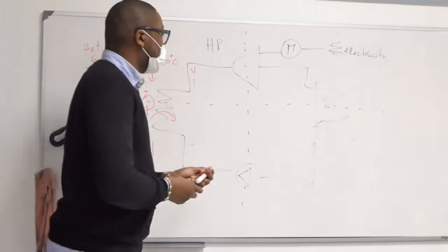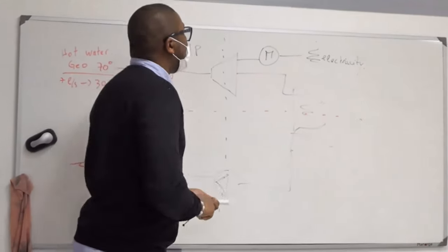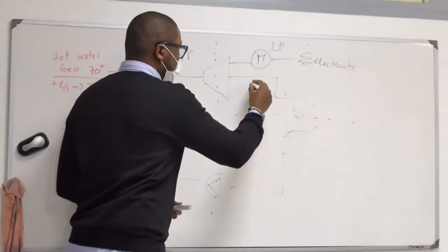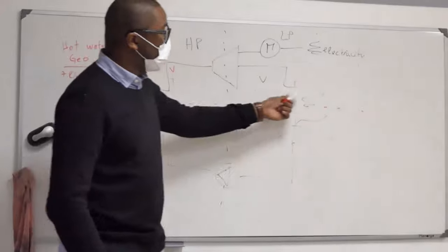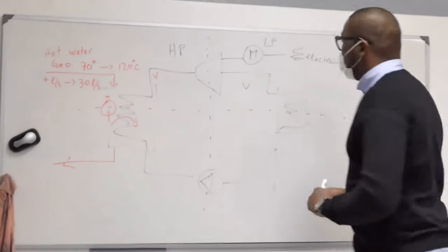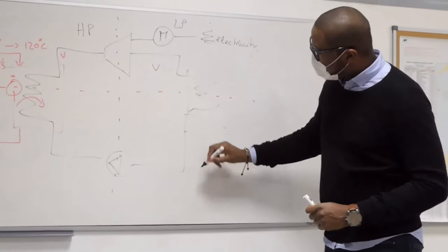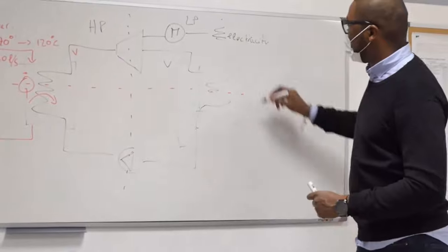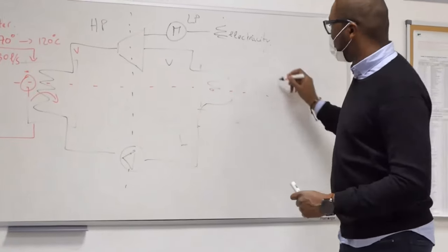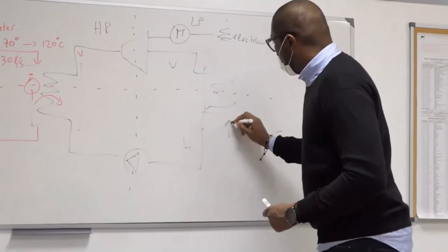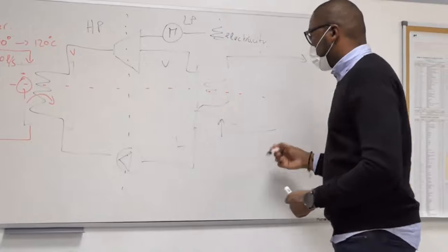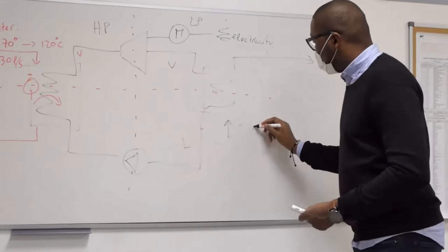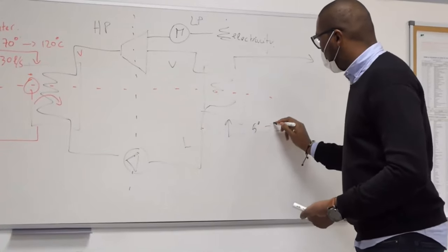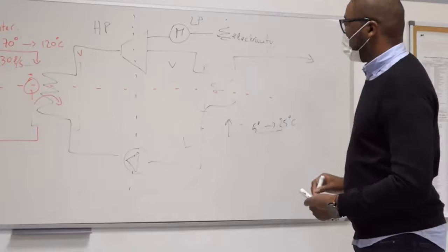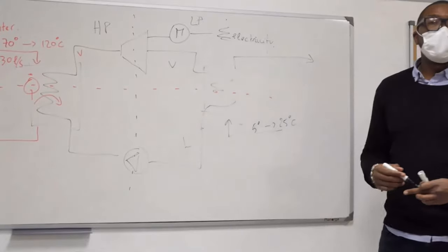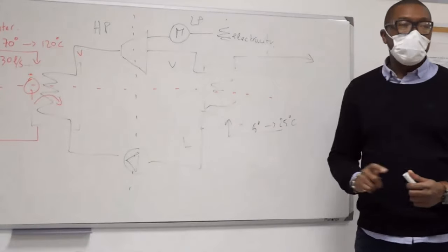After that, we will have a vapor at low pressure. This vapor will go through the condenser, and the condenser will condense the fluid, and we have liquid at low pressure. This condenser is also a heat exchanger, connected to a cold loop, depending on what we have, but we can have also 5 to 25 degrees here. And the flow depends on the thermal power we need to evacuate.